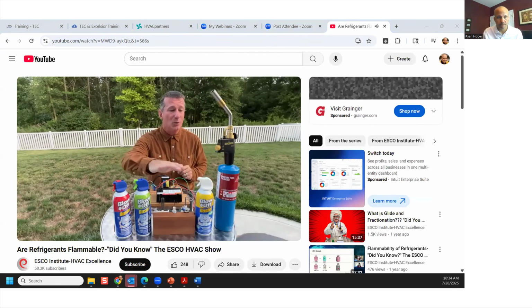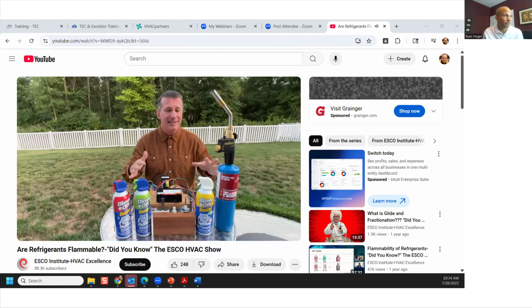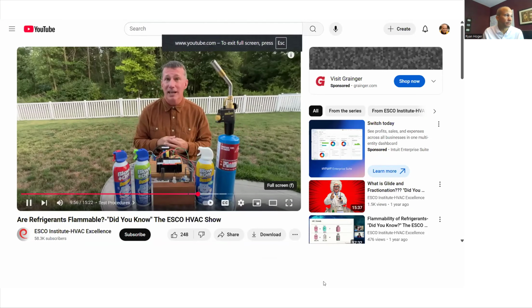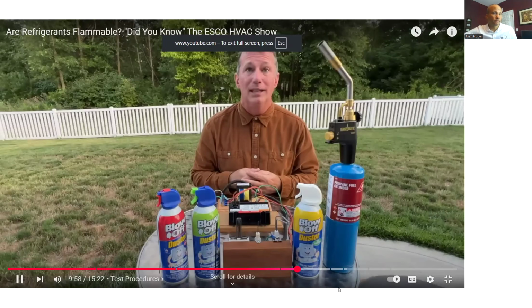Our A2, our A2L, as well as our A3 flammability chemicals. We're going to be using 3 different ignition sources that are going to be common to equipment that we know. A silicon carbide igniter, a silicon nitride igniter, as well as a direct spark ignition using a Honeywell ignition module. So we're going to see what we have for flammability on these 4 different classifications of flammable gases.